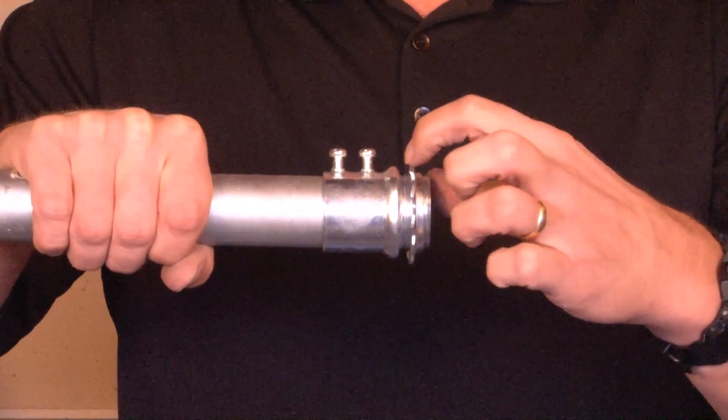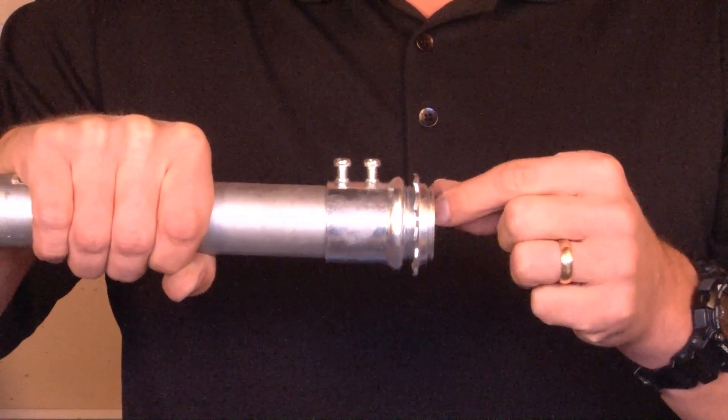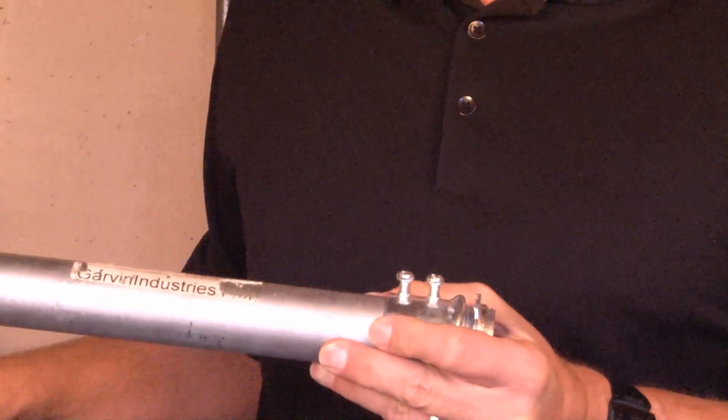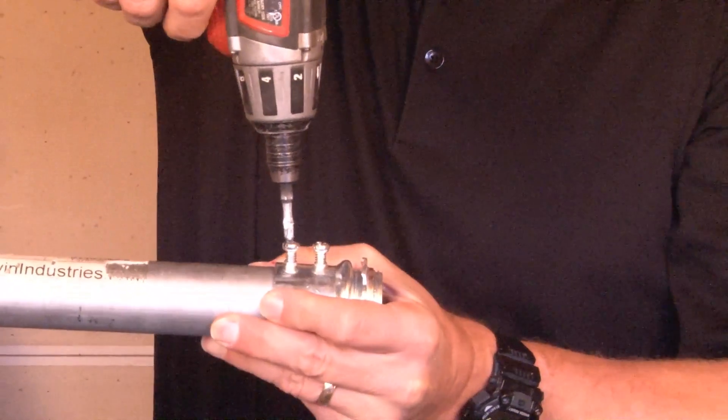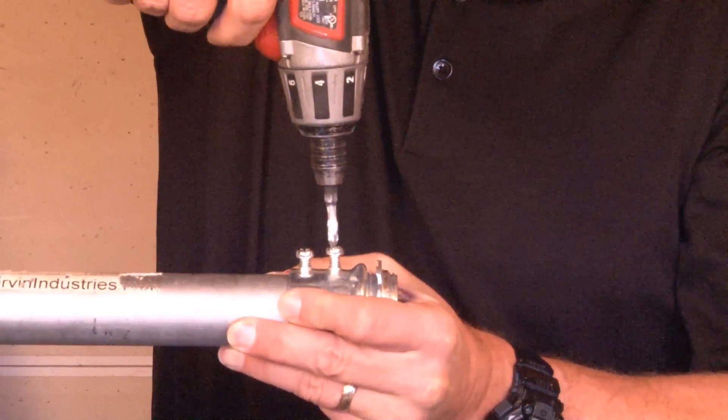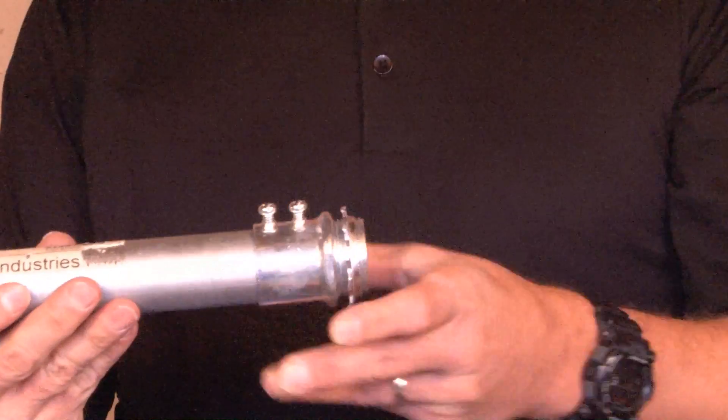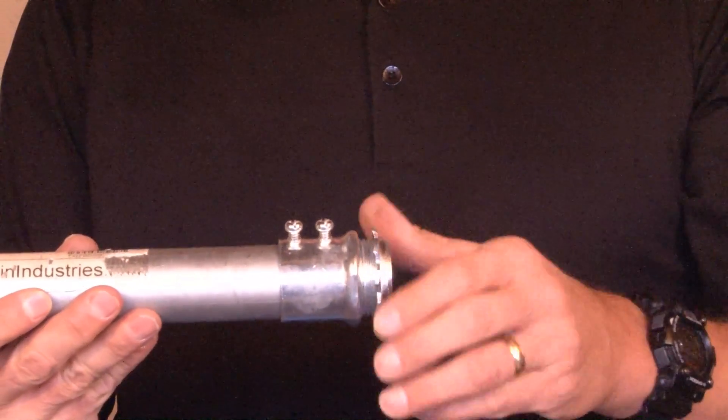It naturally hits a stopping point right in the middle of the connector and allows the installer to hold it in place and tighten the two set screws, conjoining the pipe and the connector. At this point, the installer removes the preinstalled lock nut.